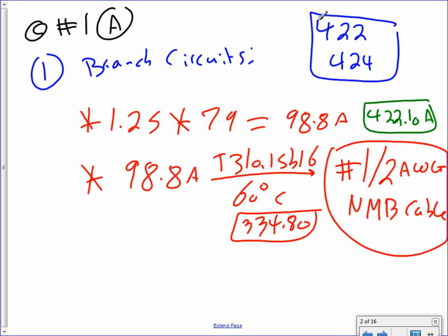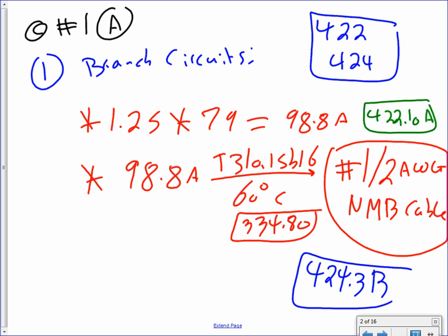The reference is also 424.3(B). It's always good to write references, guys. For branch circuits, 422.10(A) for appliances, and 424.3(B), that's for heating elements. Both of them tell you it's a continuous load multiplied by 1.25. That's all. The 334.80 will tell you for NM cable, don't you dare use more than the 60-degree column.